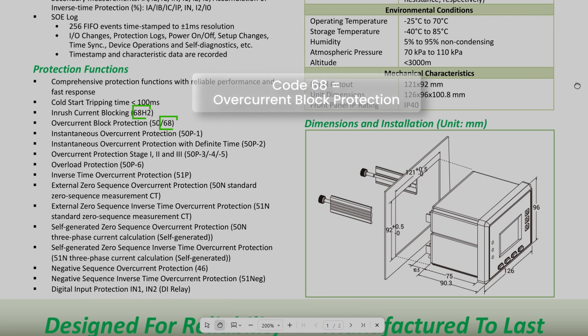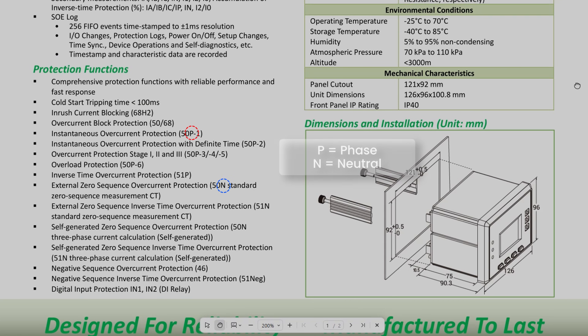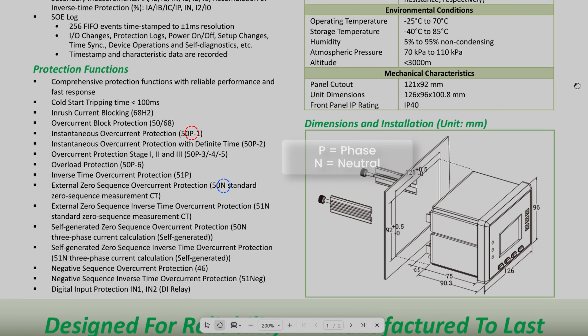68 is the blocking function that prevents another element from tripping. For example, during motor start the inrush current is high. The 68H2 uses the second harmonic to determine that it's a normal inrush current, so it blocks the 50 from false tripping when the motor starts. For the suffix letters P and N: P means phase and N means neutral.